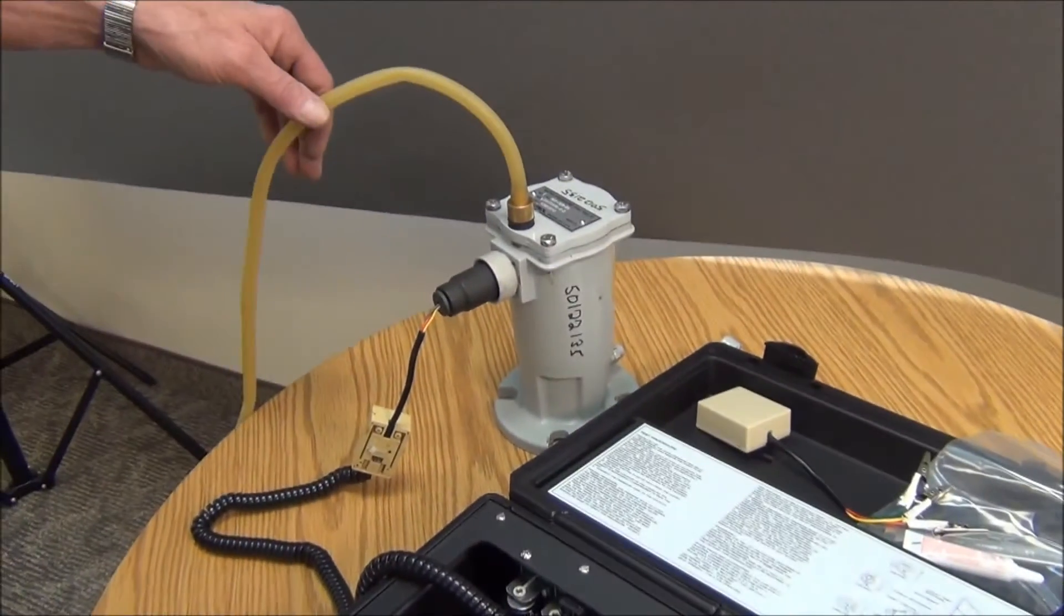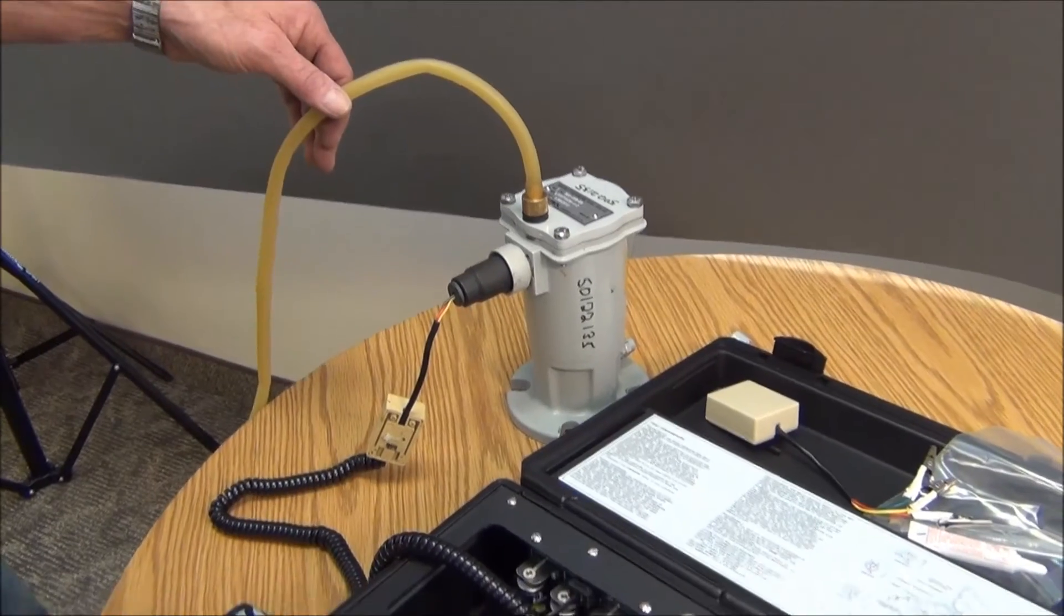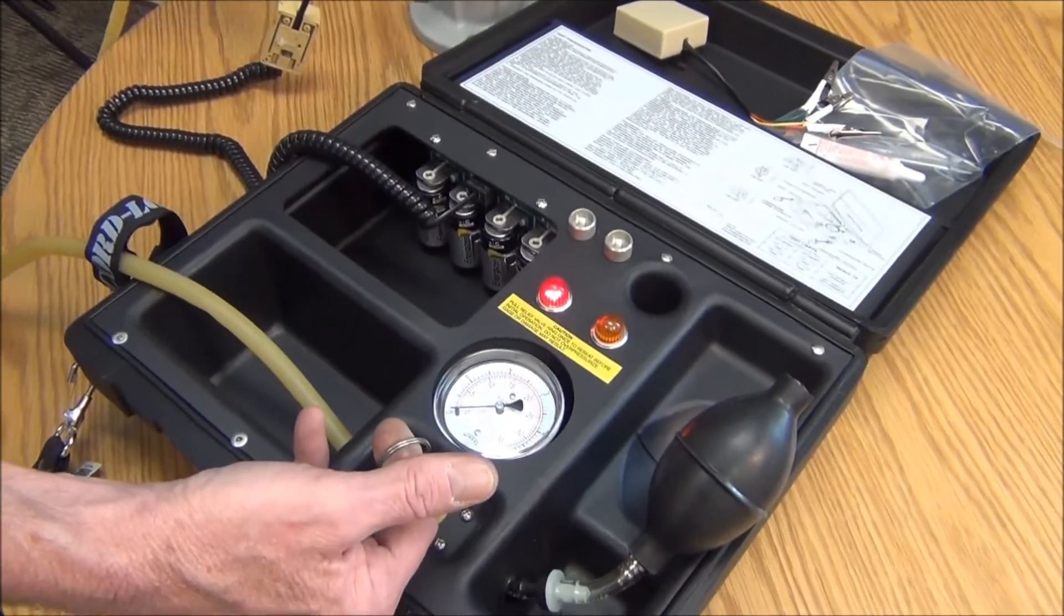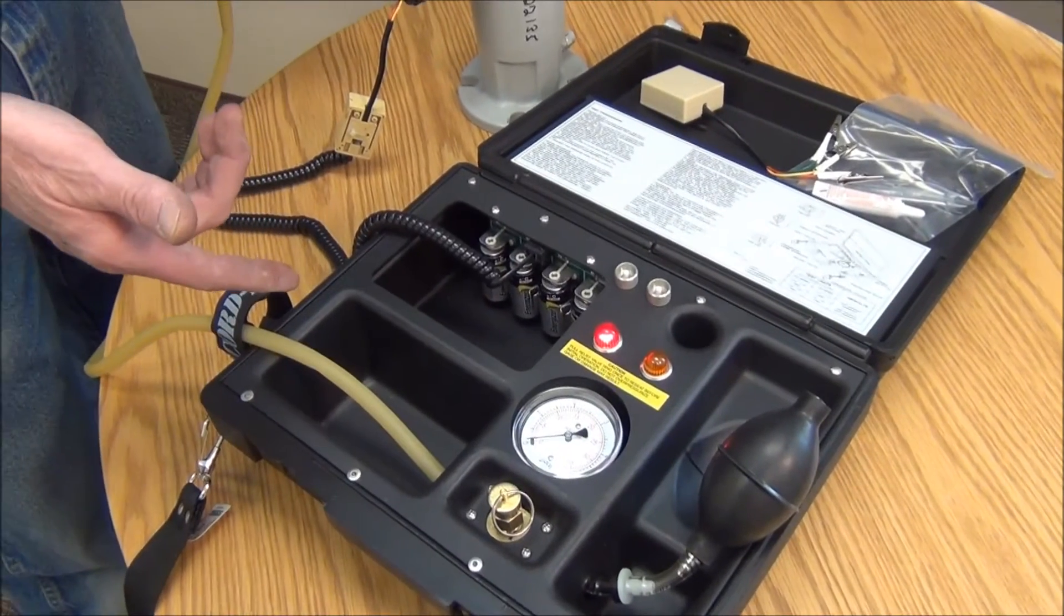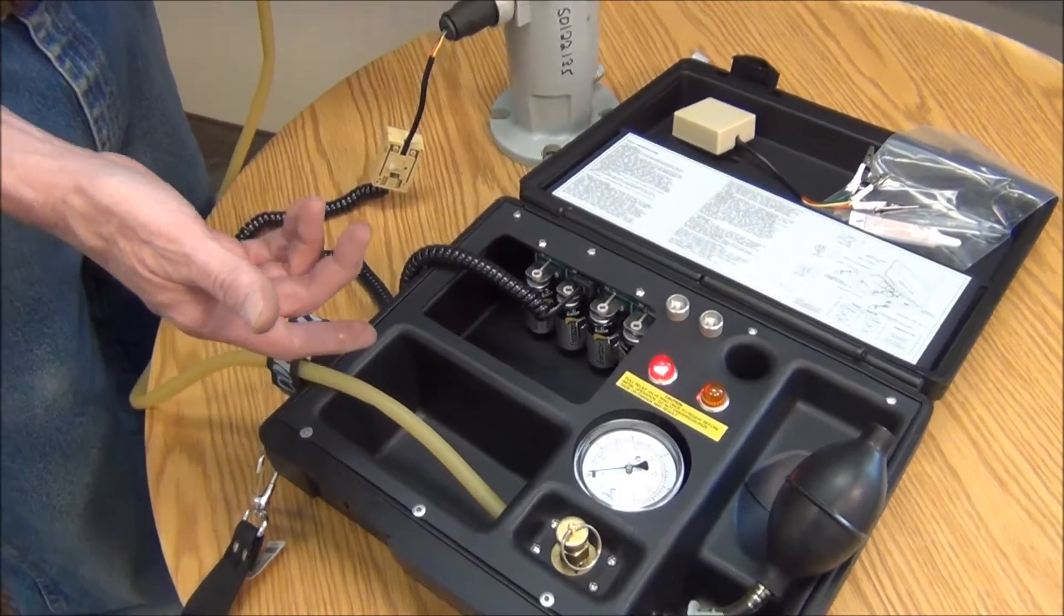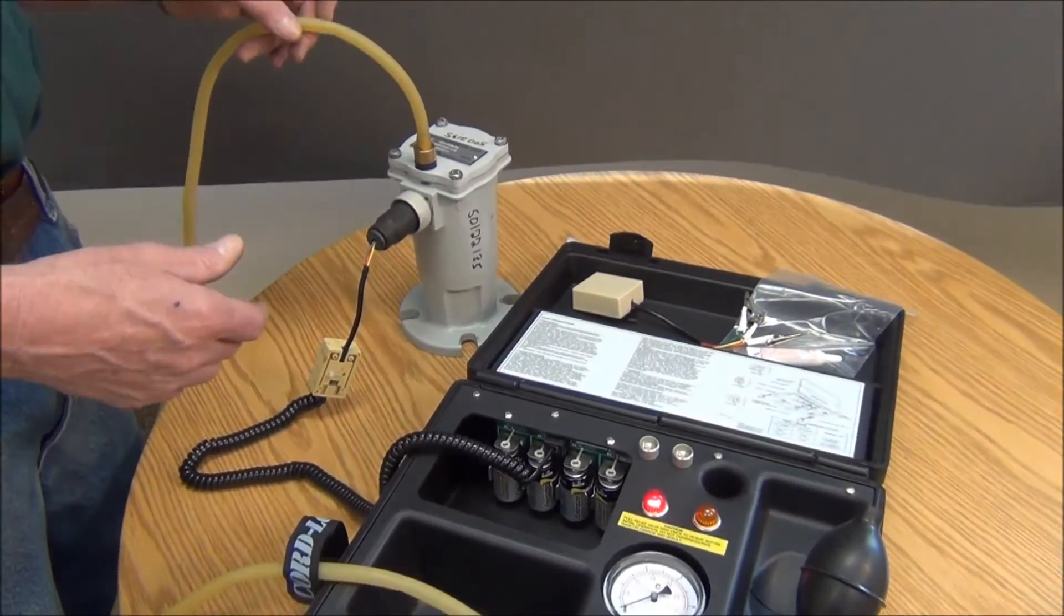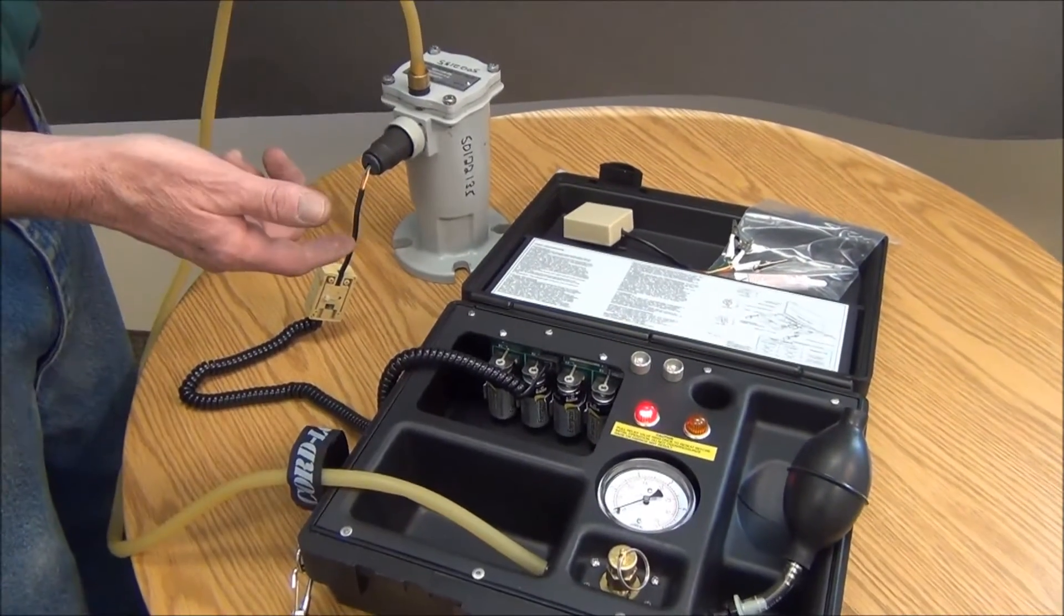This simulates roughly a 5 PSI per second increase for about half a second, and the unit tripped, which is what it's supposed to do. So this is a good unit. That's the pass test.